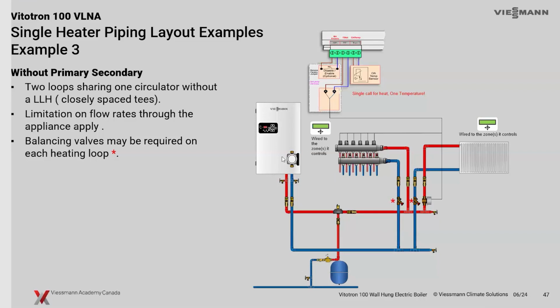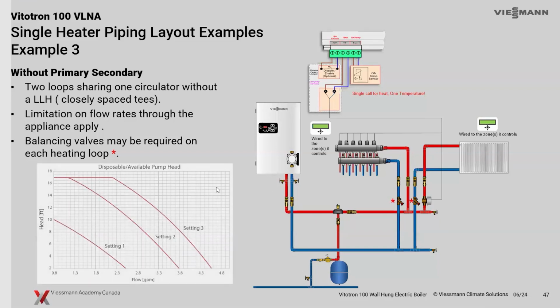We can't use the bypass for that. It's not really meant for that type of application. You'd want to set your circuits at the individual emitters, so we get the right flow rates for each one of these. All right, and again, because we're only using this single pump, you have to consider what the longest run is as far as pressure drop. Make sure we set that differential pressure bypass inside of the boiler. Once we have all these zones open and we're cooking through there, make sure that the pump stays on the knee of its curve.